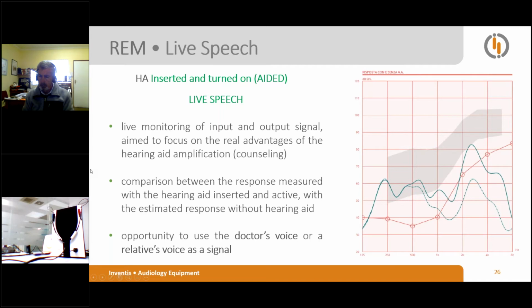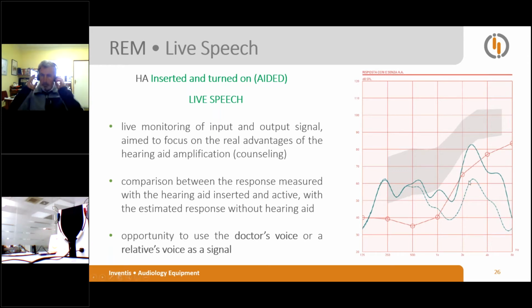It allows performing a comparison between the response measured with the hearing aid inserted and active, with the estimated response without the hearing aid. Okay, so the patient wears the hearing aid and the hearing aid is turned on. At the same time, the software can acquire two different measurements, okay? A curve which represents the listening level of the patient without the hearing aid, and how the patient may hear the sound with the hearing aid turned on, okay? So you can compare the two curves here on this graph.